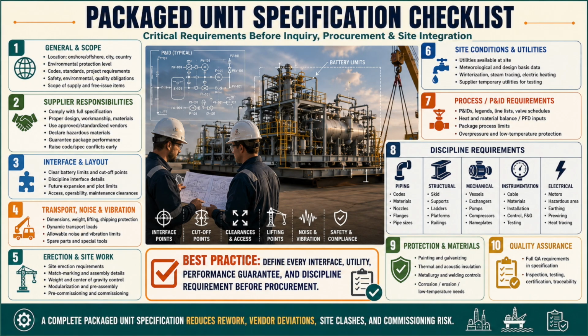Start with the package environment. Where will the unit operate? Is it onshore or offshore? Which country, city, industrial zone, or climatic region? Will it face salt-laden air, high humidity, desert dust, monsoon rain, freezing temperatures, seismic forces, or marine exposure? Environmental protection cannot be treated as a generic note. It determines enclosure ratings, corrosion protection, material selection, winterization, ventilation, electrical classification, and equipment life.